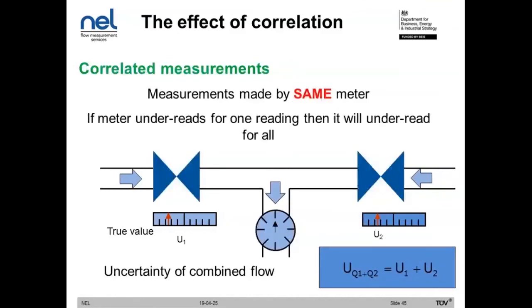However, if you find that the meters actually have a systematic error applied to them, so maybe they've both been calibrated at the same source and a systematic error has been introduced, then you have correlated uncertainties, and it wouldn't be appropriate to combine them using the root sum squared method. So for correlated uncertainties, the method of combination is just a simple addition. So rather than squaring each of the values and then adding them together and then finding the square root, you just add them together. And the reason for this is that both of these devices in this case have the same bias. They both have a negative error and a tendency for those uncertainties to propagate. So this is how they are resolved.